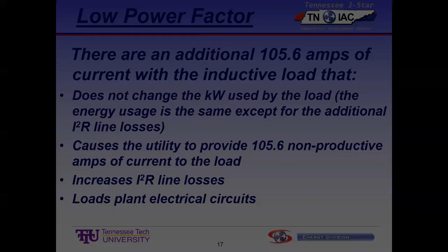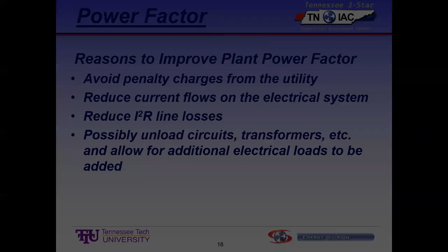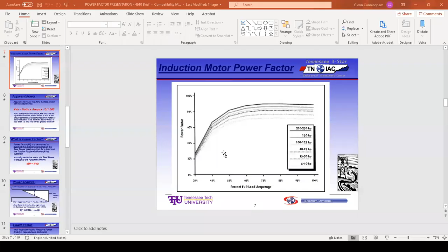That can be a huge savings for a plant, because maybe they just want to add a 50-horse motor. They need to add another pump down here, but they've got to feed it. The MCC is loaded, so they correct power factor on 3 or 4 different motors served through that MCC. That reduces the current, and then they can add another motor, and they don't have to do a project to expand the electrical system, which is horrendously expensive. You've got to add another MCC, you're probably talking $200,000. You could add a 50 horsepower pump for maybe $10,000 or $15,000. So there are lots of reasons why a plant might want to do this. So the reasons: avoid penalty charges, reduce current flows in the electrical system, reduce I²R, possibly unload circuits and transformers so you can add additional loads. Okay, that wasn't so painful, was it?